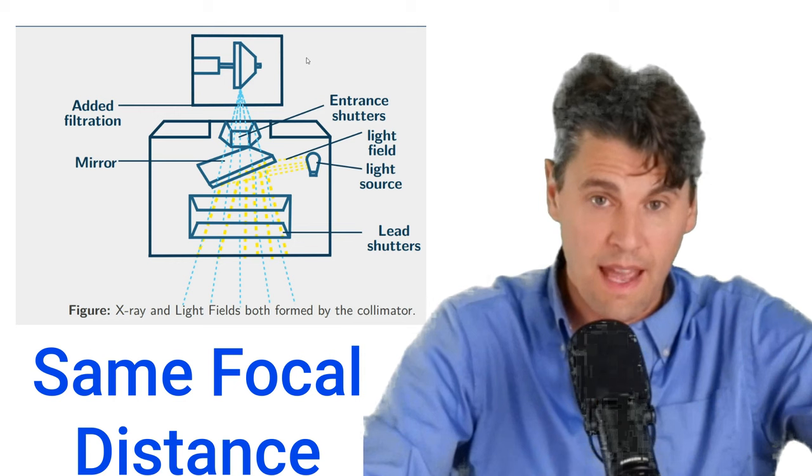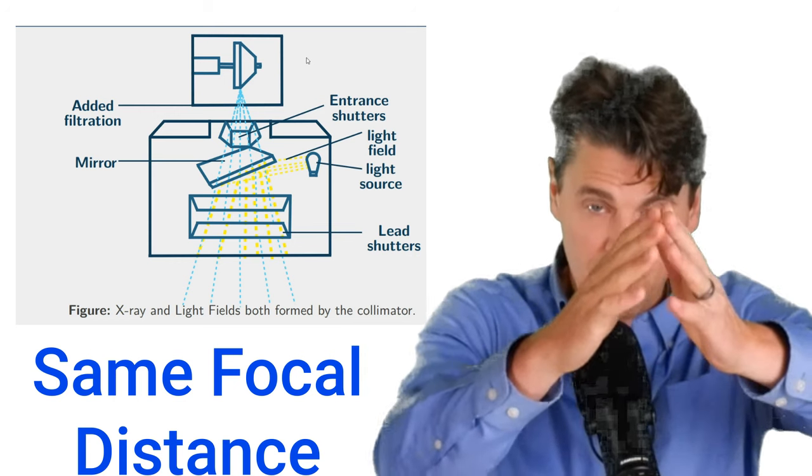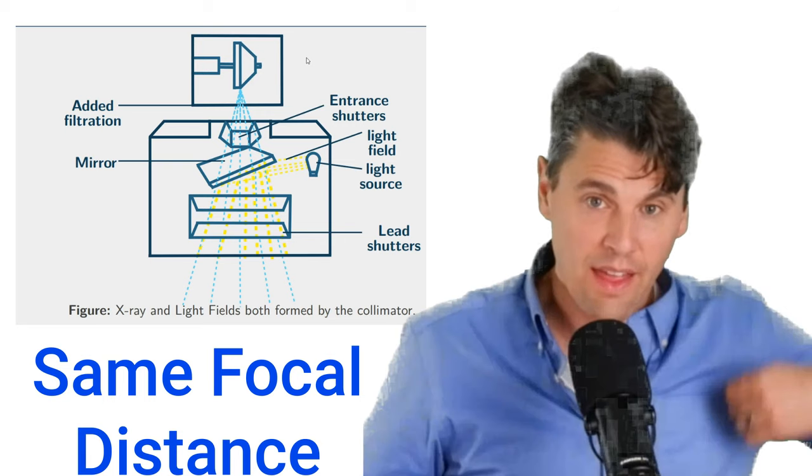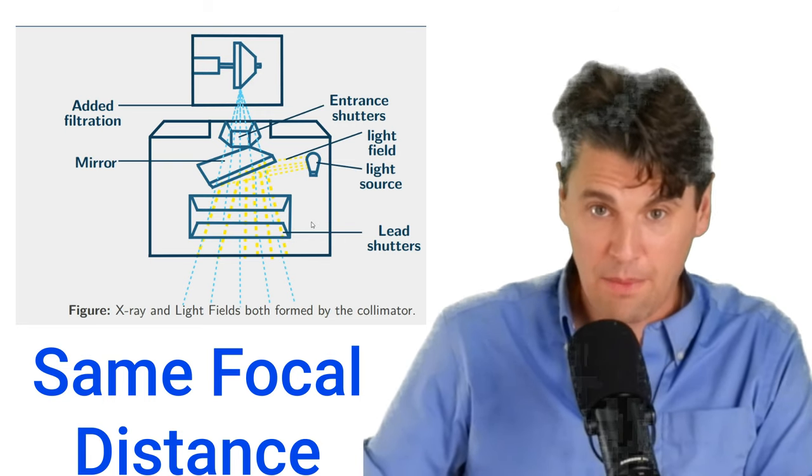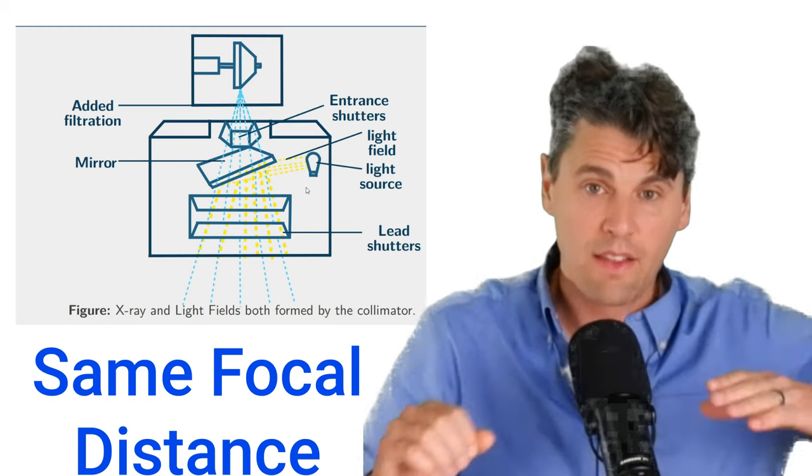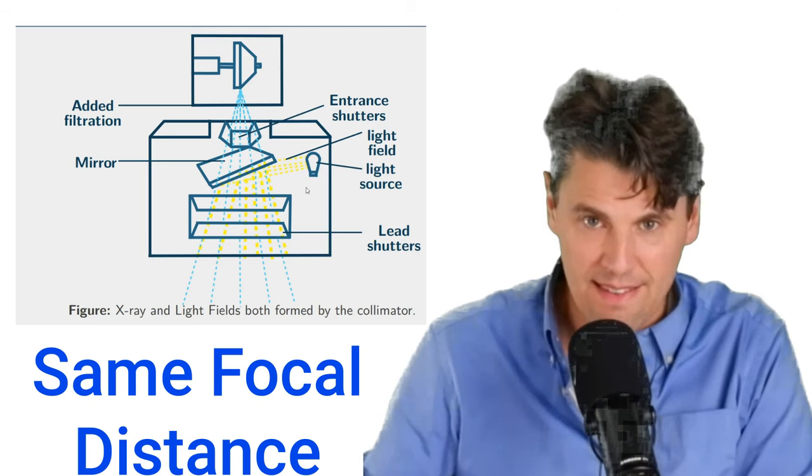That light can essentially travel the same path that the x-rays will be traveling. The light that's at the outside will be blocked by the lead shutters or the collimator, and then the light that's on the inside is going to pass through in the same way as the x-rays.